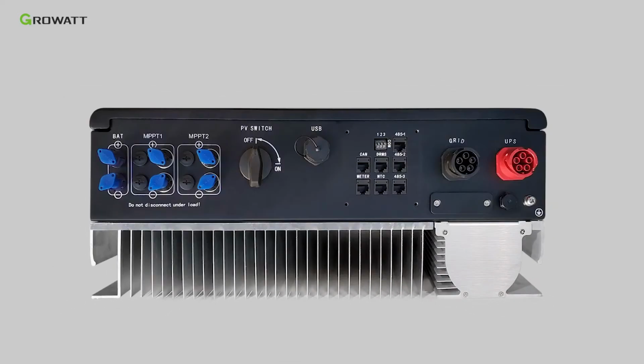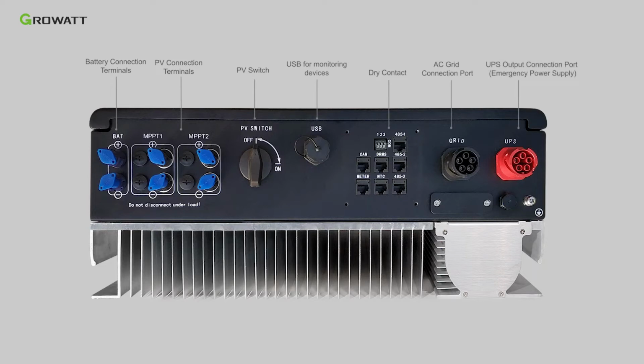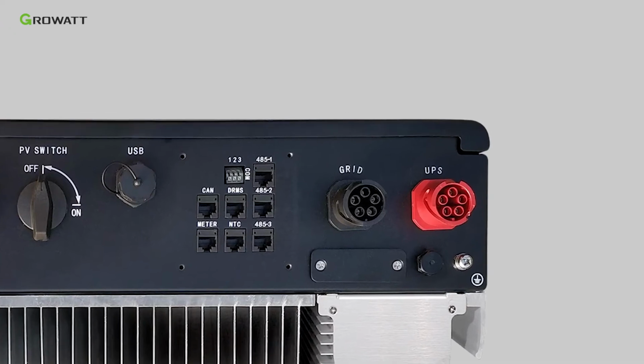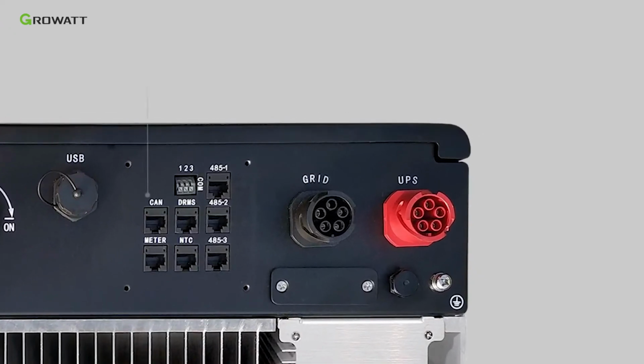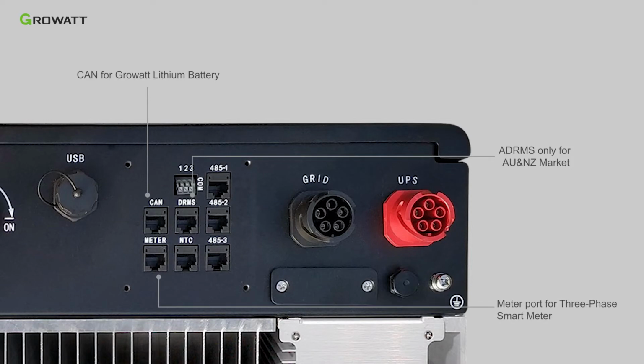There are some connection terminals including battery connection terminals, PV connection terminals, PV switch, USB for monitoring devices, dry contact, AC grid connection port, UPS output connection port, and emergency power supply.